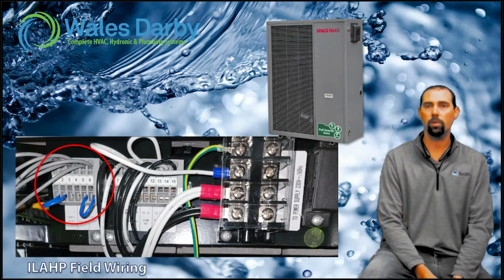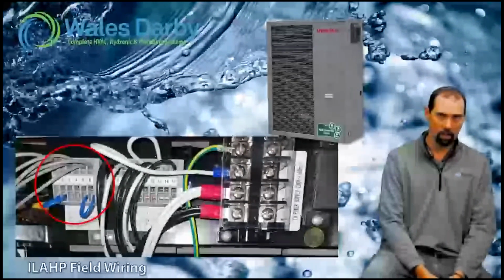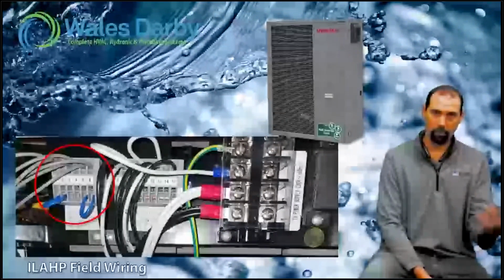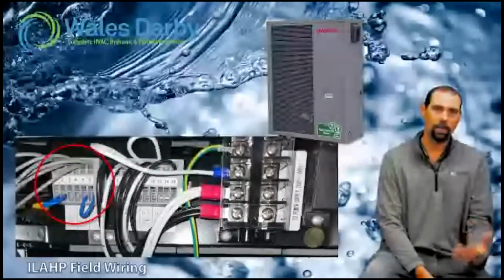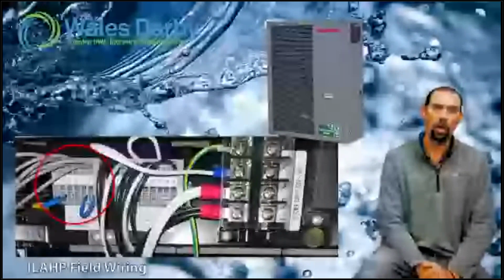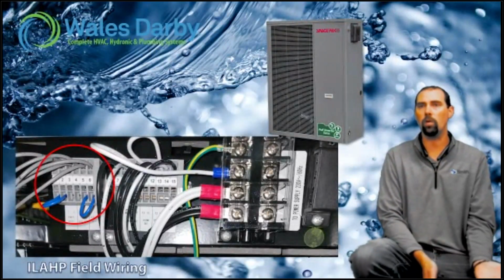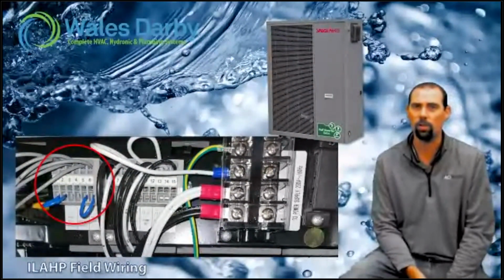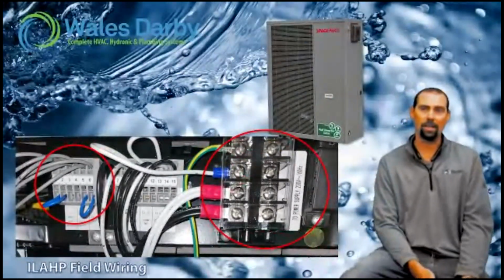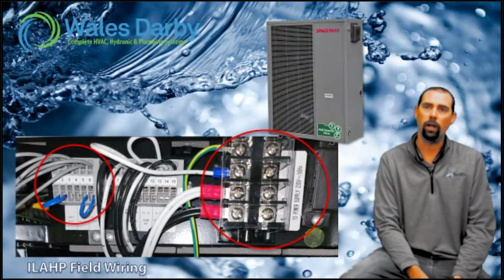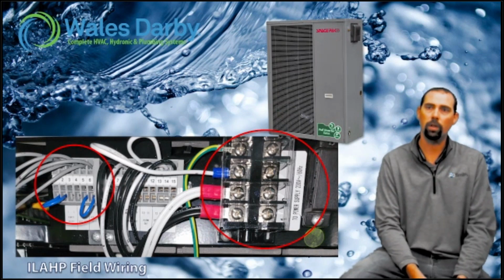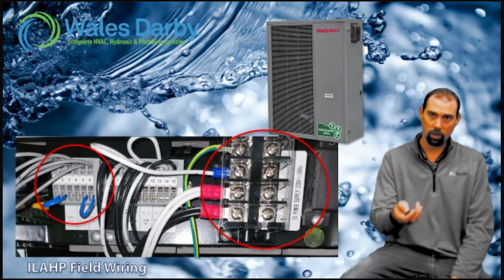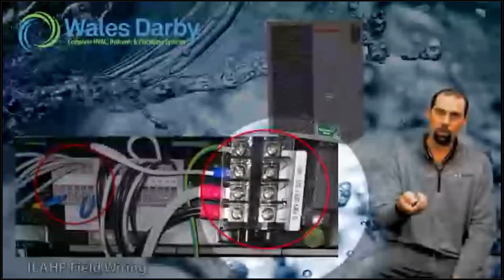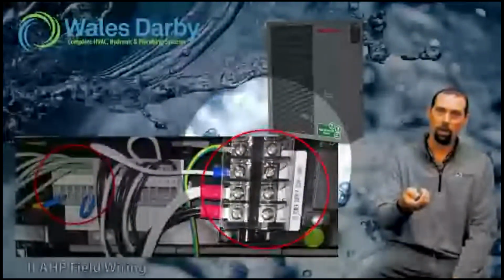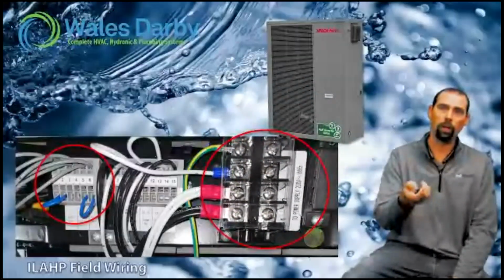4 wires go into a control you're going to see in a few seconds. Very easy to control. We do have some other contacts there if we want to do some auxiliary stuff, but that's going to be your basic layout on most applications: your on-off and your heating or cooling reversing valve. So those are both dry contact, low voltage wires. And then on the line side, we're talking 4 wires. We got our 220, our 1 and 2 there, and then starting from the bottom, we got 1 down here, 2, that's our second leg of our 220. We're gonna bring in a neutral, and then we're gonna bring in a ground.